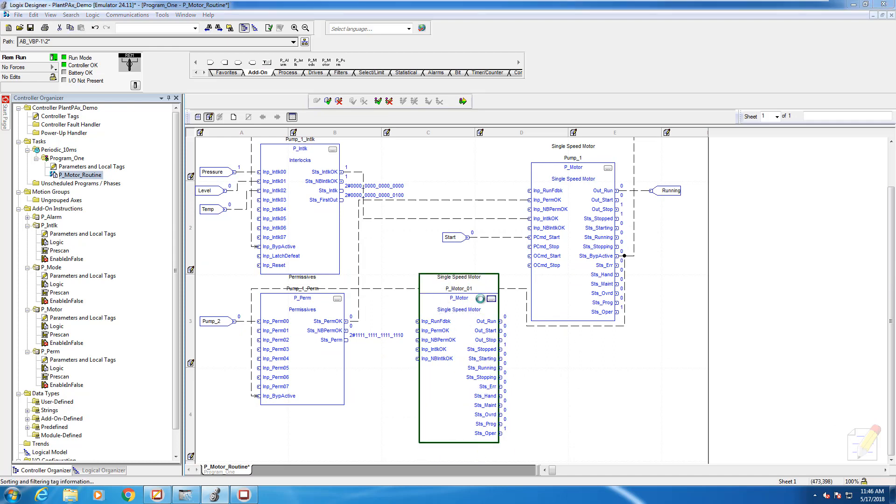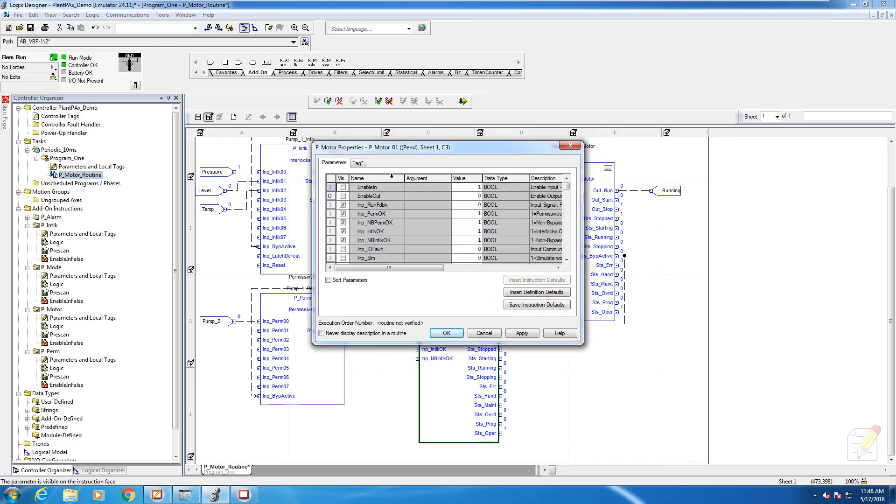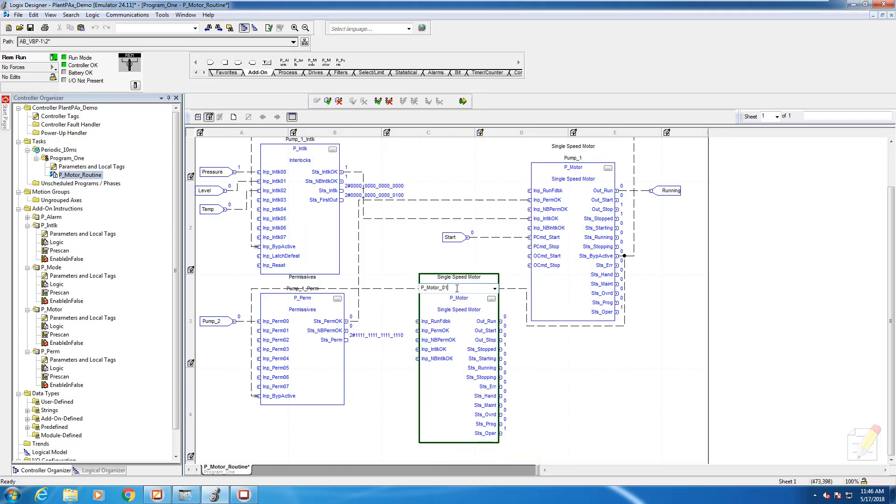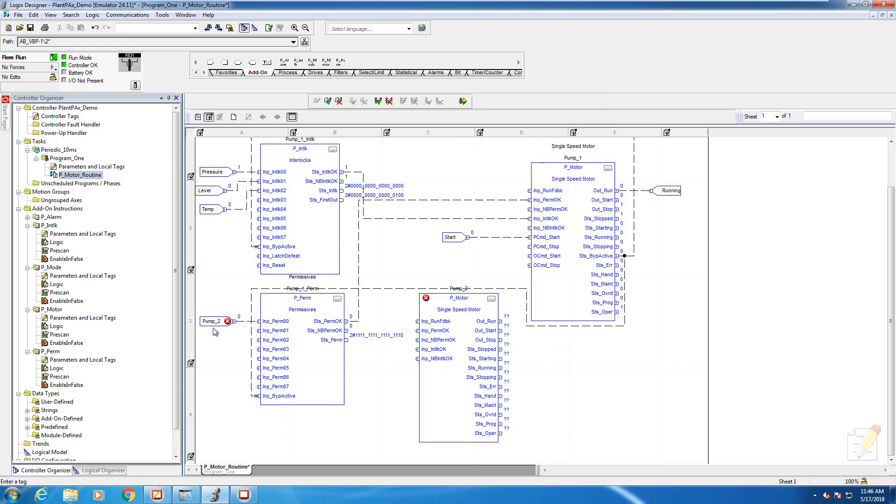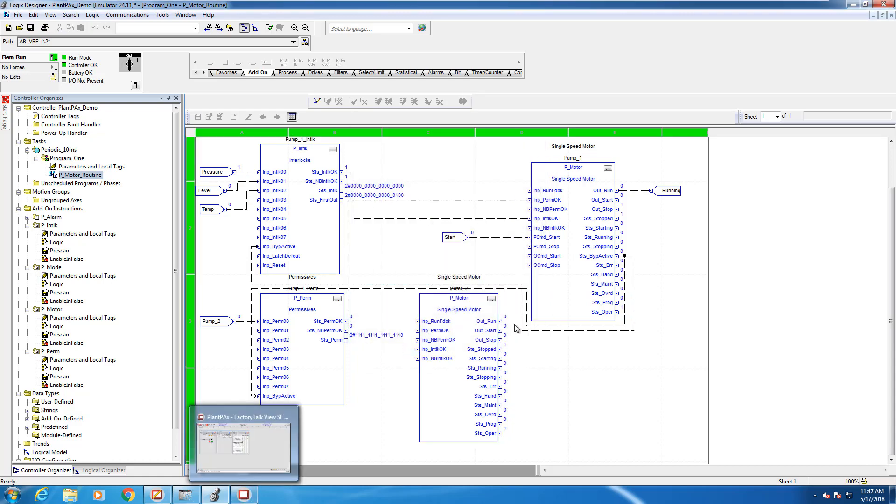What you'll see me do here is add another P motor instruction, and we're going to use that as the permissive for our pump one. This means that our pump one will not be allowed to run until the pump feeding it is also running.